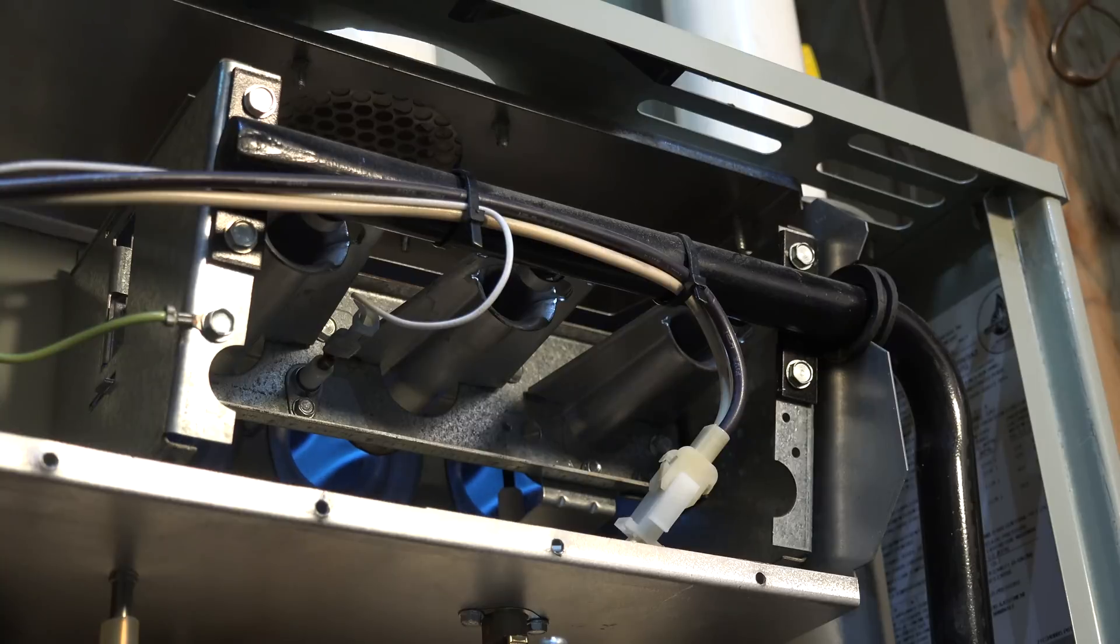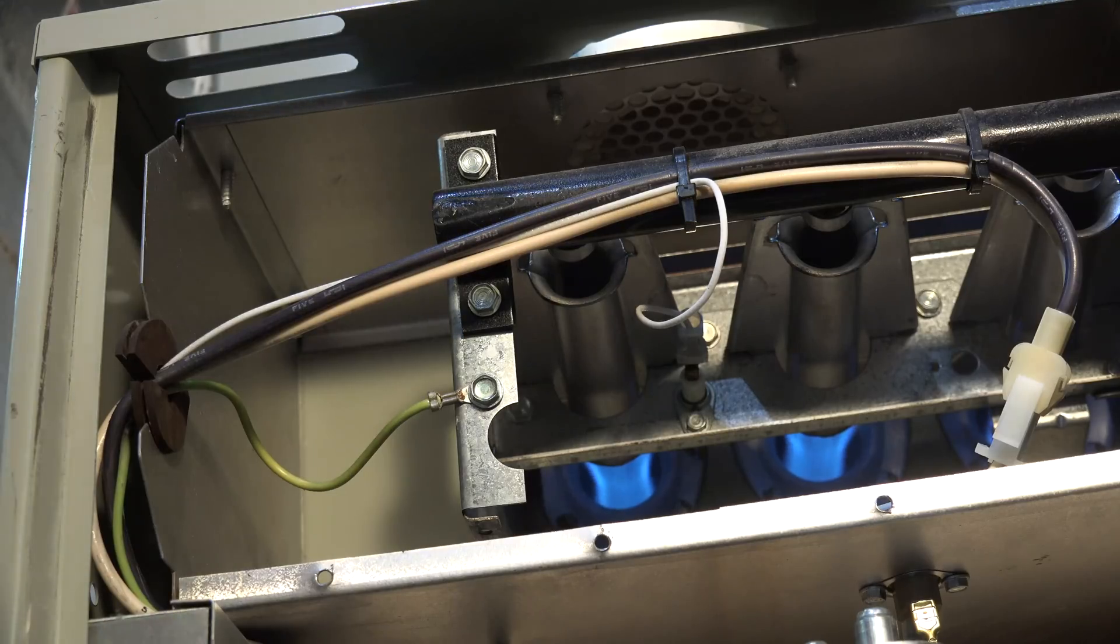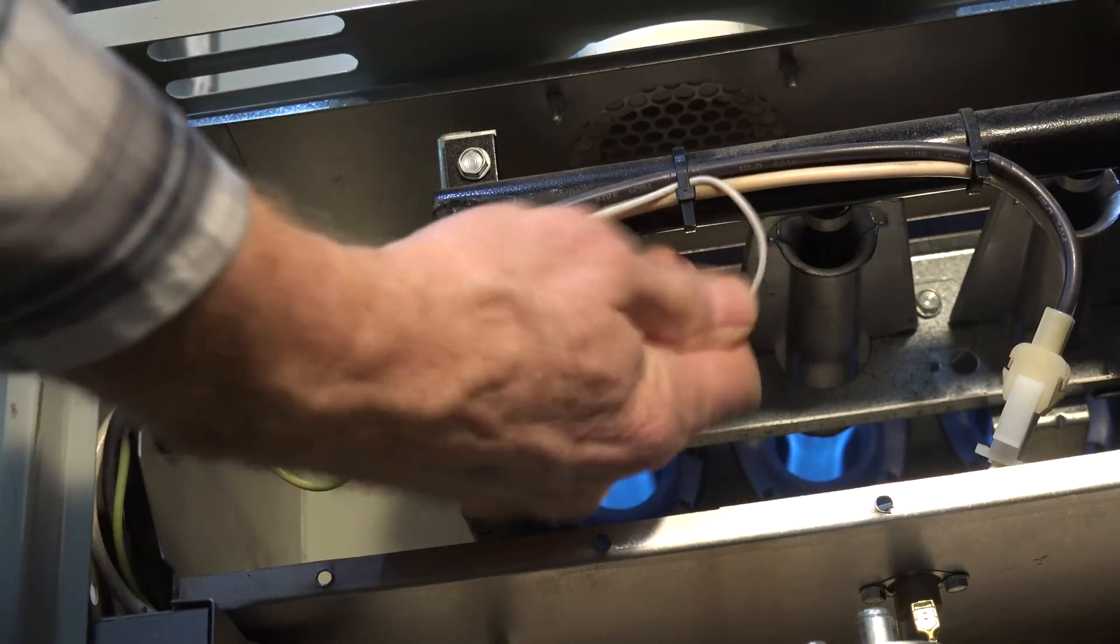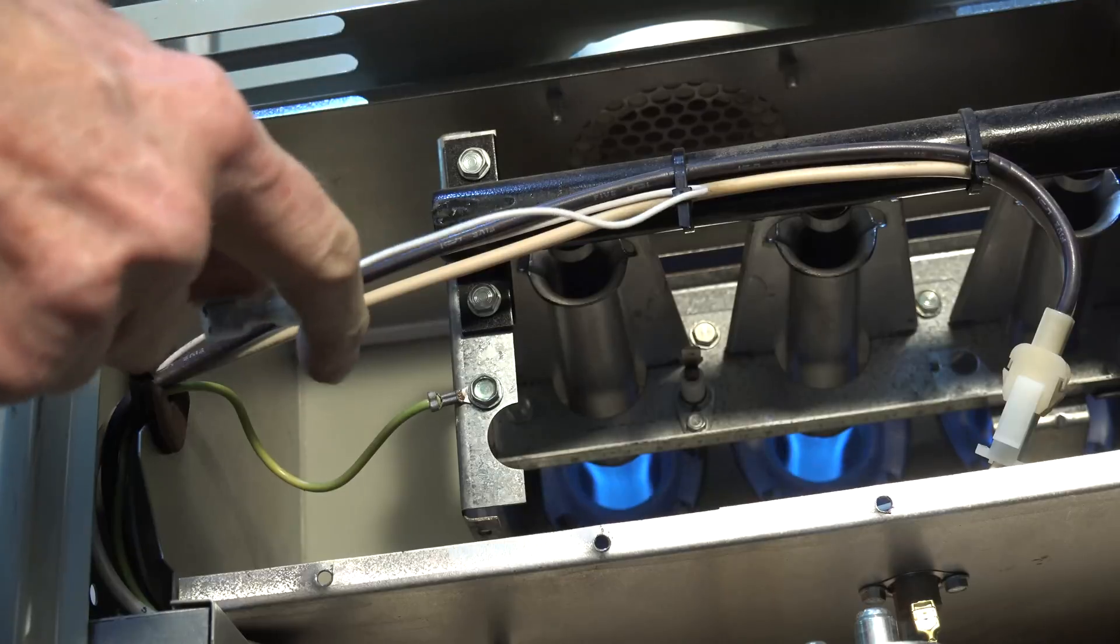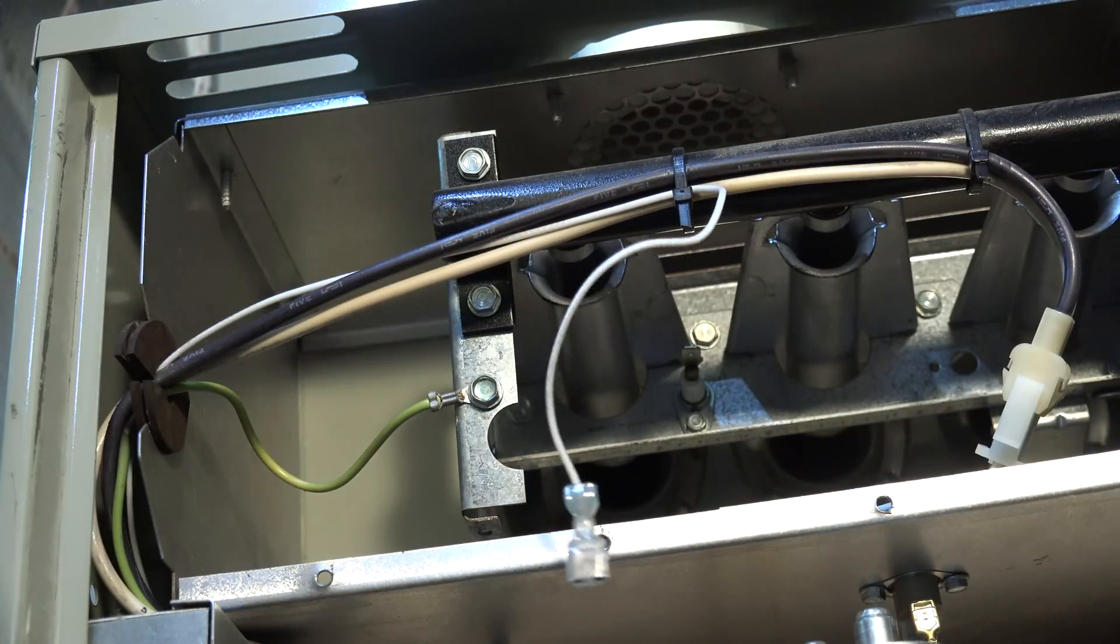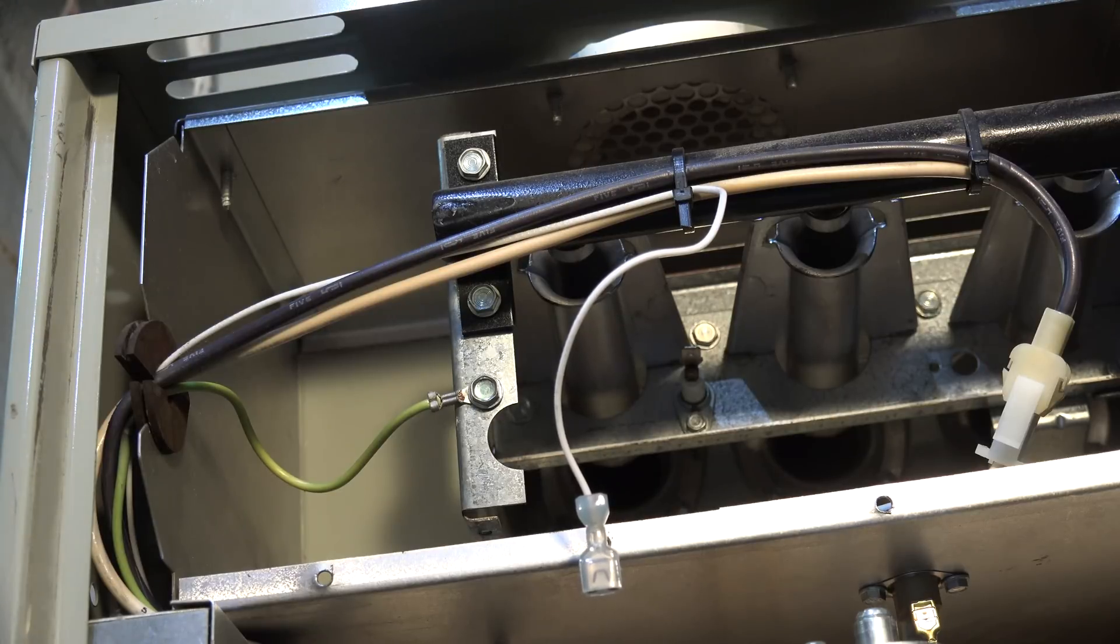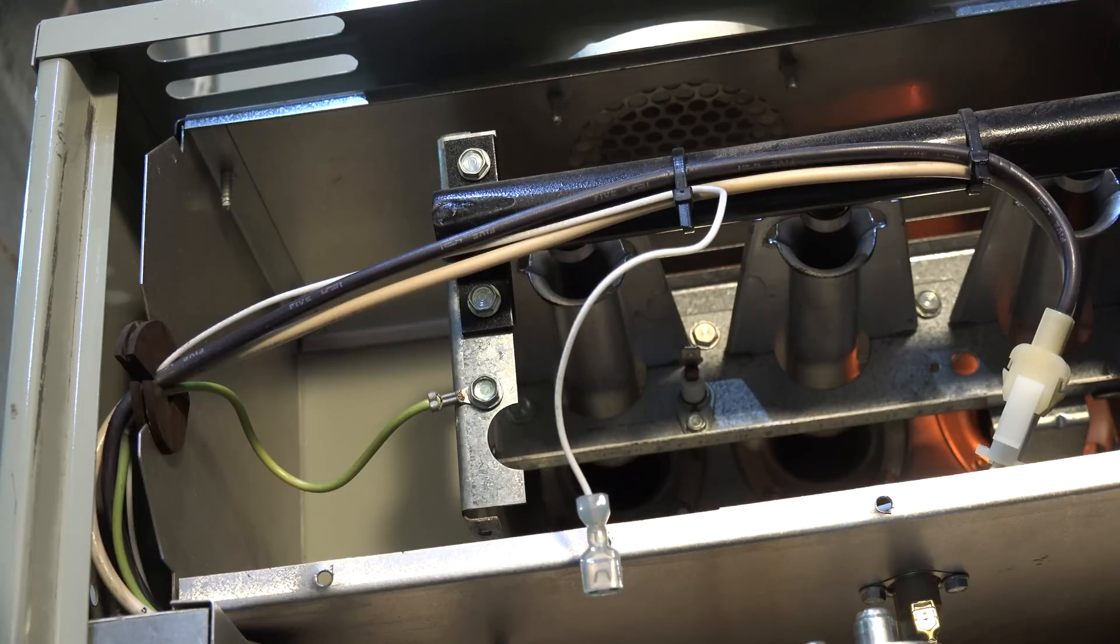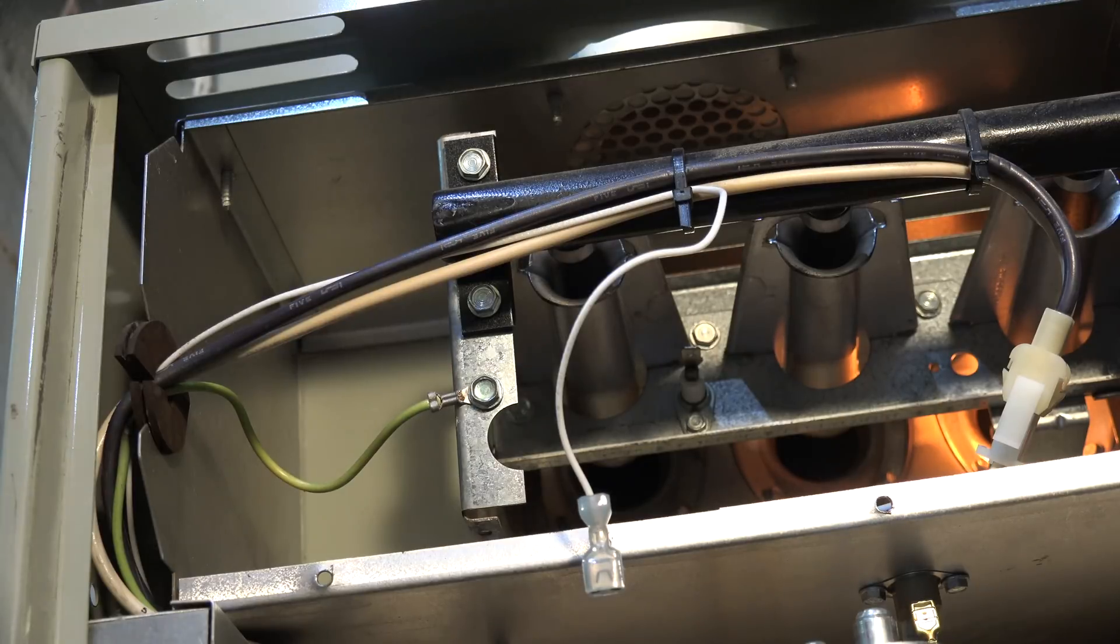Now one of the things I'd like you to check while you're doing this is to be sure that the flame safety operates. Now here over at the flame rod, I'm going to pull the wire off. Okay, it shut off just like it should. A second, maybe less, it should shut off. Always test this when you first fire up something after you've replaced some sort of part on it, every time.